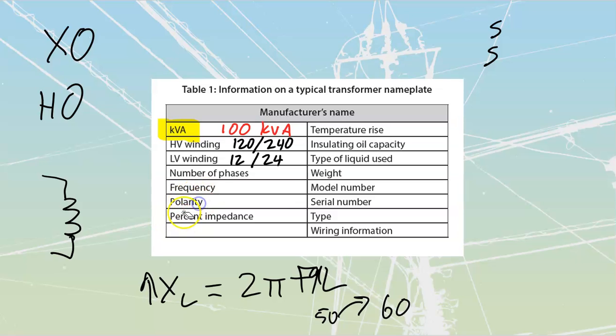Percent impedance is going to be a big one. Sometimes it's written as just percent Z. If you see percent Z on there, Z stands for impedance, and the percent sign means percent impedance. It is going to be critical that you find and understand this value for calculating fault currents, specifically for calculating interrupting ratings for circuit breakers. Because the fault current is the maximum amount of current that could flow through your transformer under a fault.